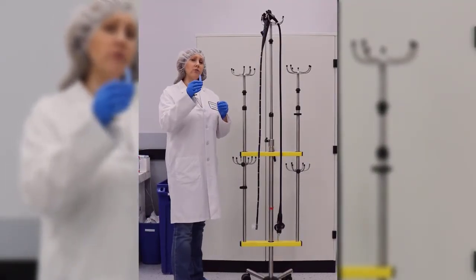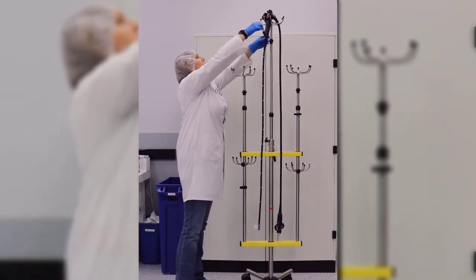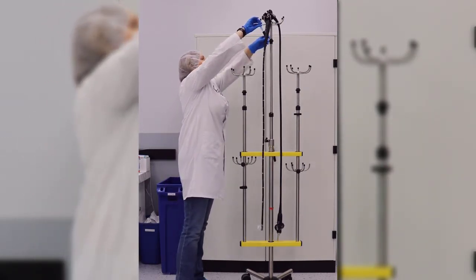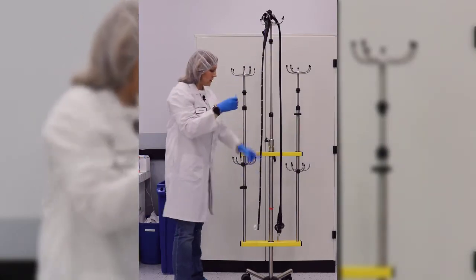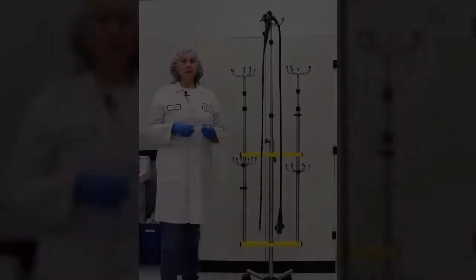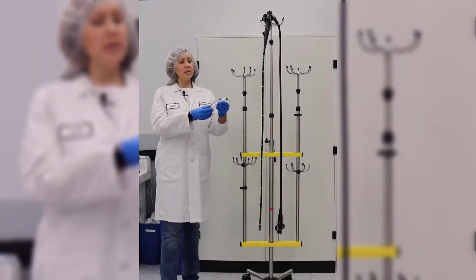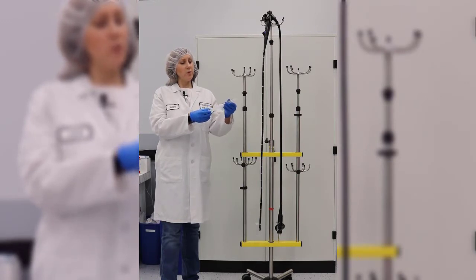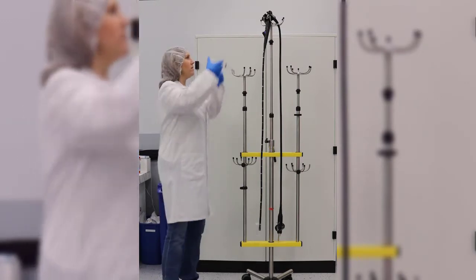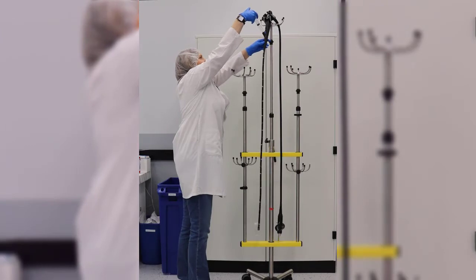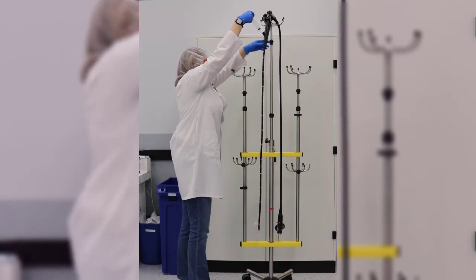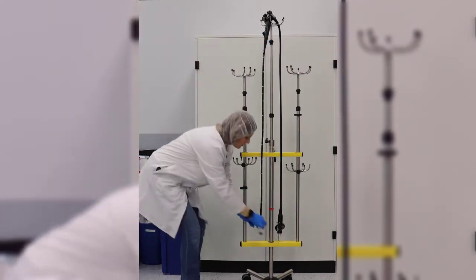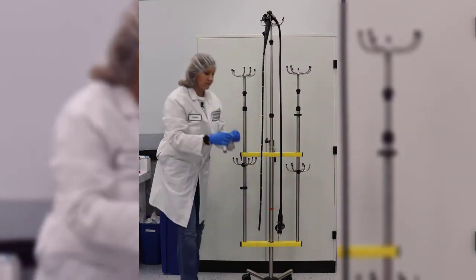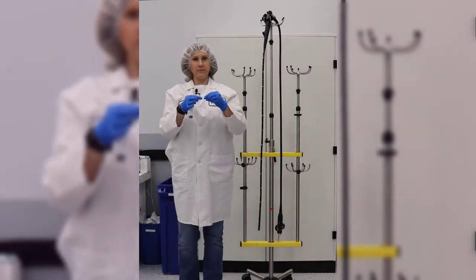So we're going to take our prepackaged vial and forcibly squeeze all the water down into the channel, and the water will be captured down into the Ziploc bag. So now we're going to take our syringe and pull in 30 cc's of air, and purge the biopsy channel with the air. Make sure all the water is captured into the Ziploc bag. Take it off the distal tip and close up the bag.